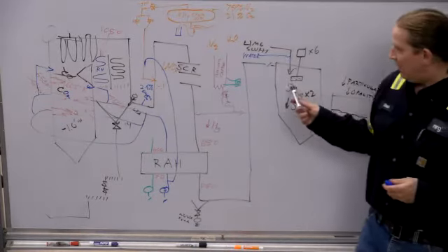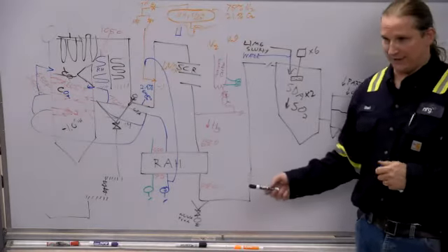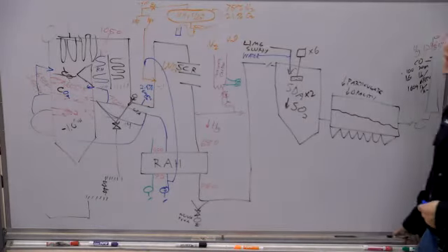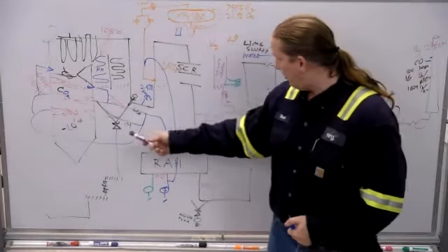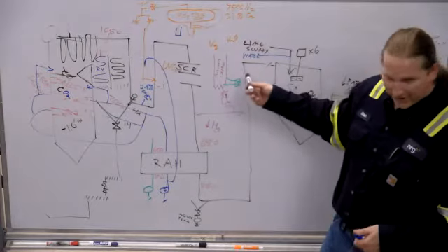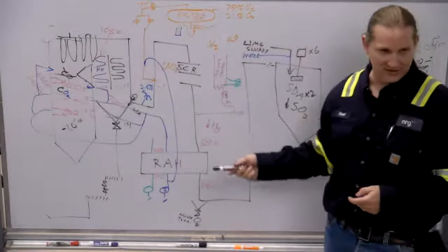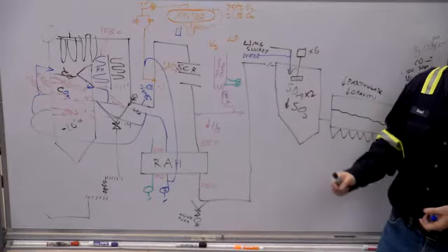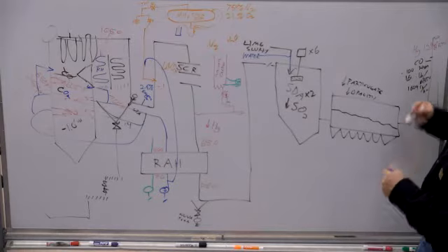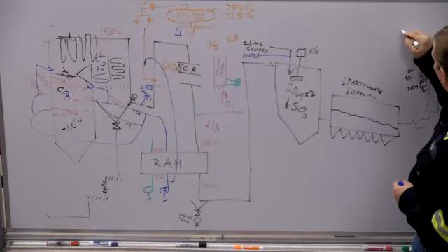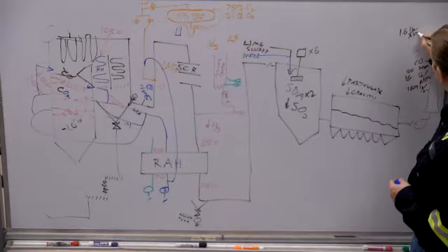So the coal quality makes a big difference. Some mines have more sulfur in them than others do, and so some trains of coal will have a lot more sulfur on the inlet that we have to clean up. And our limit isn't based on a percent. It's not saying you've got to reduce it by 80%. It's saying you've got to reduce it below this level. And that level is 1.6 pounds per million BTU.